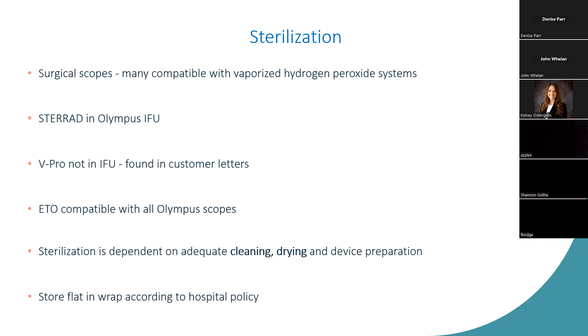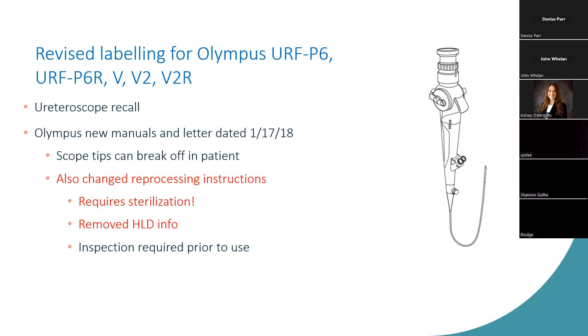But the way this came through as a safety notice, it was a recall for these models because there were reports of parts of the scope coming off inside patients. So of course, people zeroed in on that and paid attention to that. They didn't necessarily pay attention to the fact that suddenly the IFU changed where reference to HLD was removed, and now what was stated was that sterilization was required. This is a really good example of how monitoring for the latest information and having the latest IFUs from manufacturers is so important.